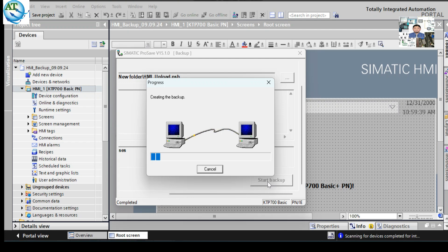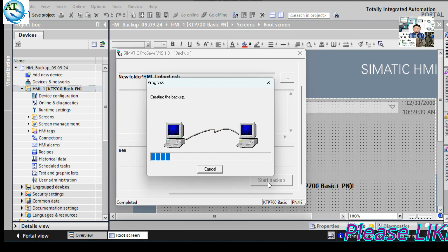Just to mention again: nowadays in industrial automation systems, this type of HMI — the Simatic KTP-700 Basic — is most commonly used. It is very user-friendly. When used with the S7-1200 PLC, it is very easy to upload and download by using the same interface cable connected directly from the PLC to the laptop, with the PLC directly connected to the HMI. This method is also available for Simatic S7-300 and S7-400 systems — in the same way, you can upload or download the HMI program using the same Ethernet interface cable connected HMI to PLC, PLC to laptop.